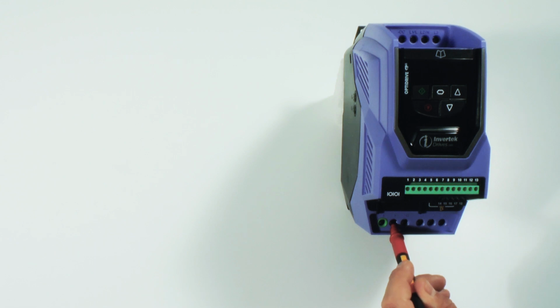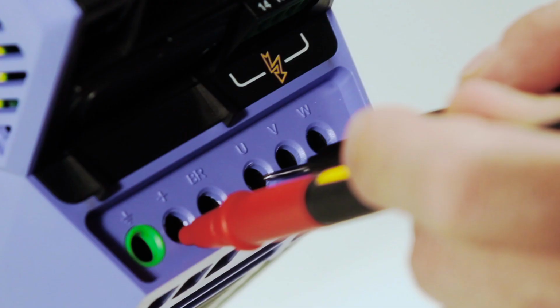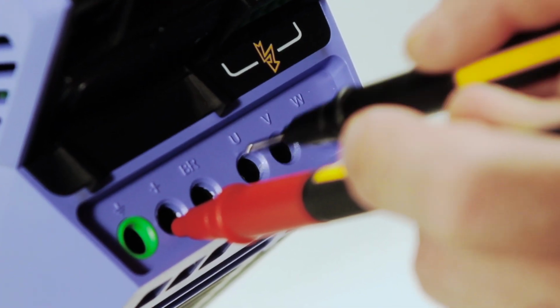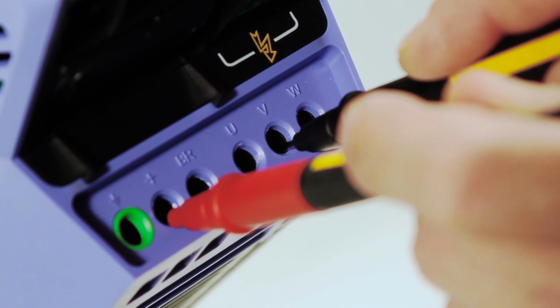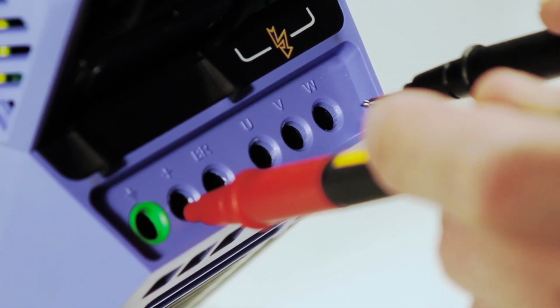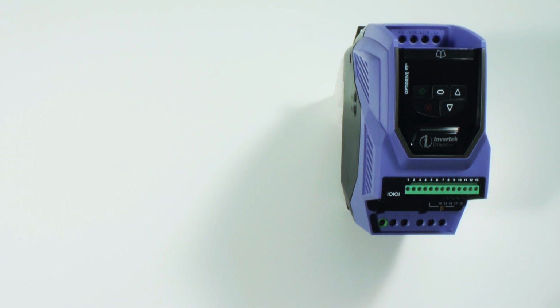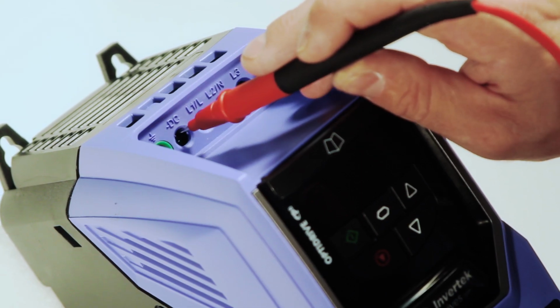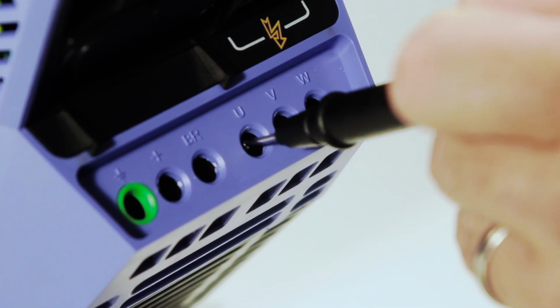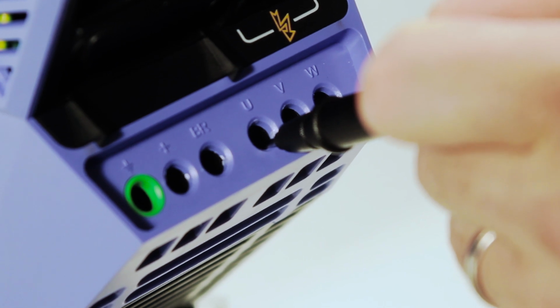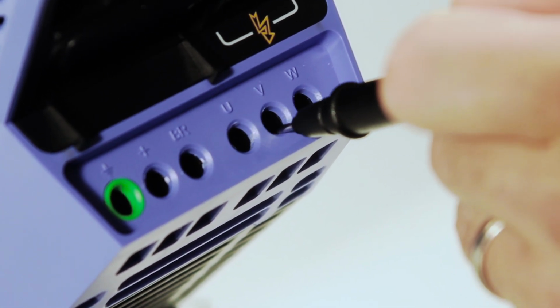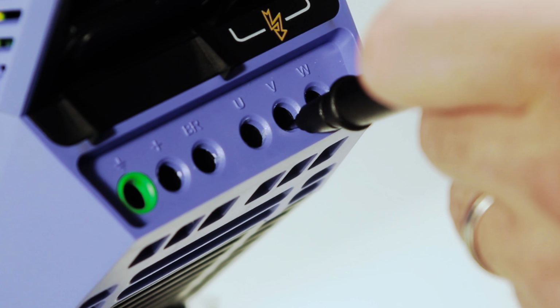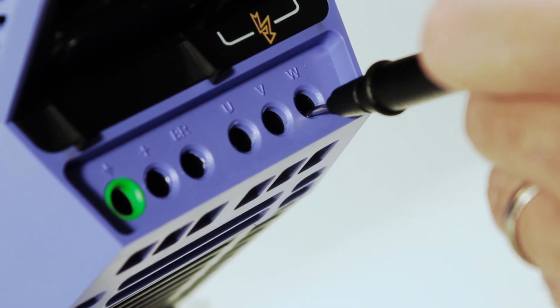Place the red lead on the plus DC bus point and measure with a black lead to the U phase, V phase and then finally W phase. Place the red lead on the minus DC bus point and measure with a black lead to the U phase, V phase and finally the W phase. Complete the service request form with your readings.